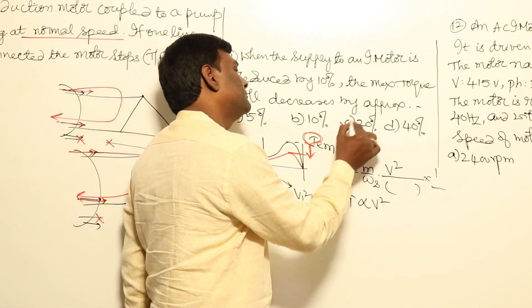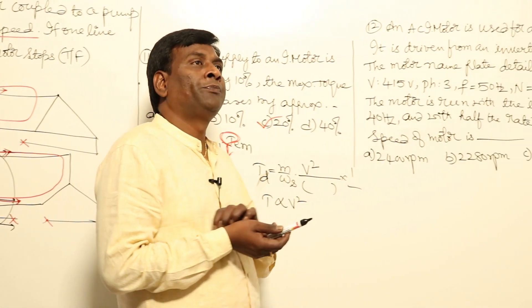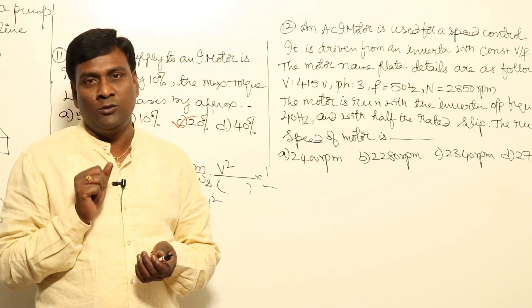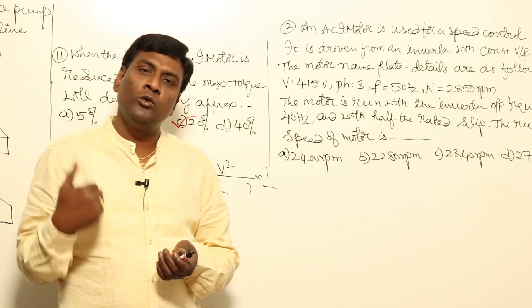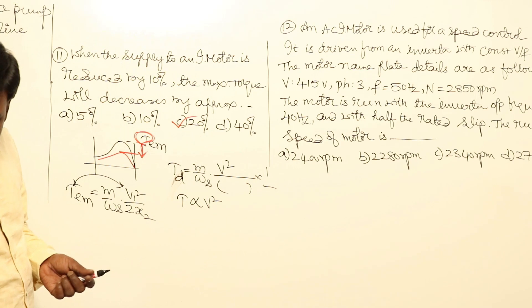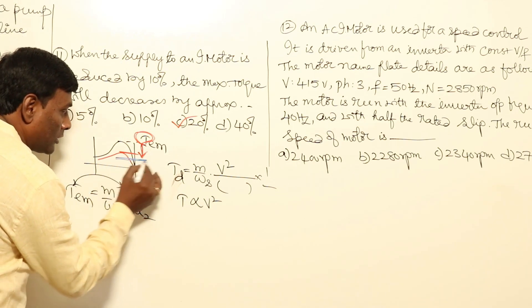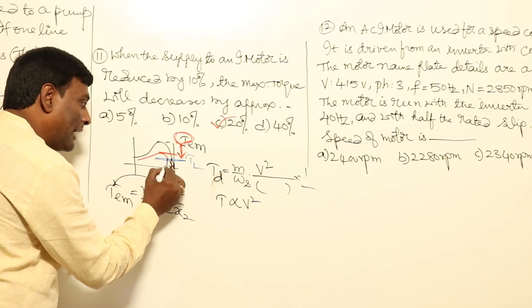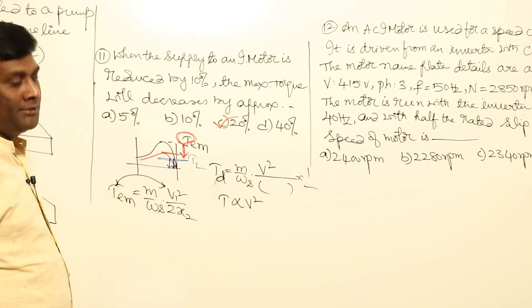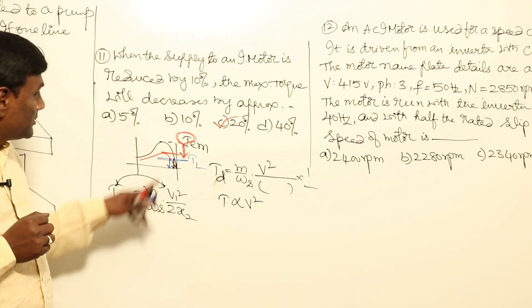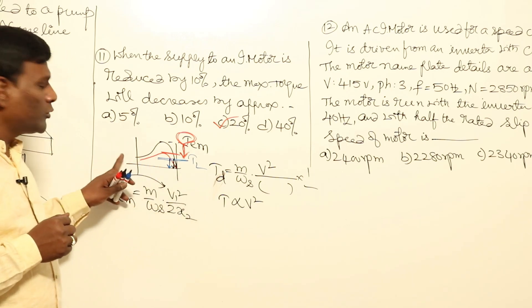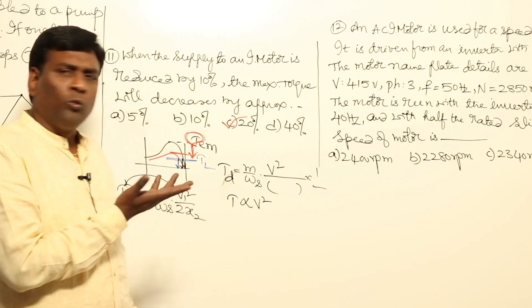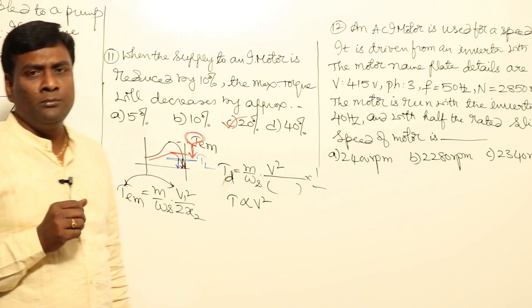That means roughly 20 percent. If an induction motor is designed for 400 volts and you reduce the voltage, you can maintain speed control — but we should not use this method because the pull-out torque will be reduced by the square of the voltage ratio. Starting torque is similarly affected. Point to note: speed control by voltage variation is not preferred. We will directly solve problems using the torque equation.